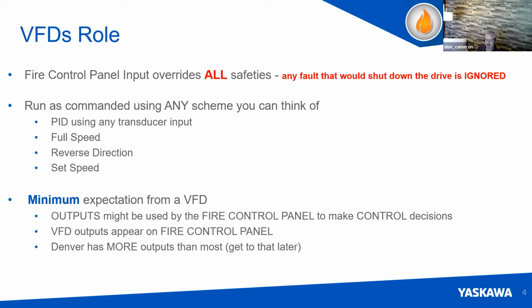So what's key is that you can run in any scheme you can think of. You can use what you have already from the fire mode input, or you could use a separate transducer input. You can tell it to run at full speed. You can tell it to reverse direction. You can run it at a fixed speed. There's no limitation as to what you can do. Whatever it is you need to do, you can have the drive do that based on that one single digital input.